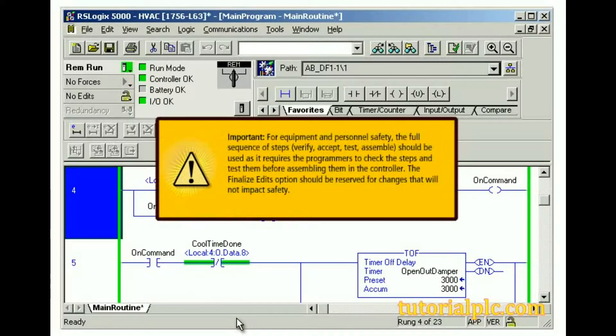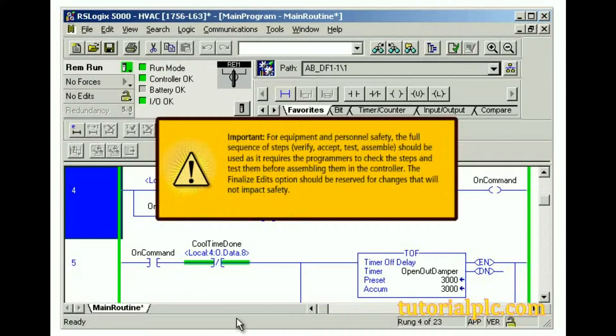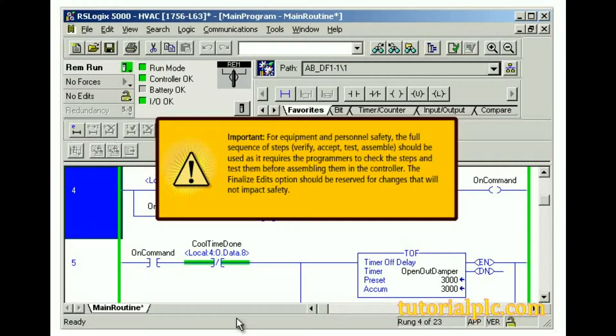Important! For equipment and personnel safety, the full sequence of steps Verify, Accept, Test, and Assemble should be used, as it requires the programmers to check the steps and test them before assembling them in the controller. The Finalize Edits option should be reserved for changes that will not impact safety.